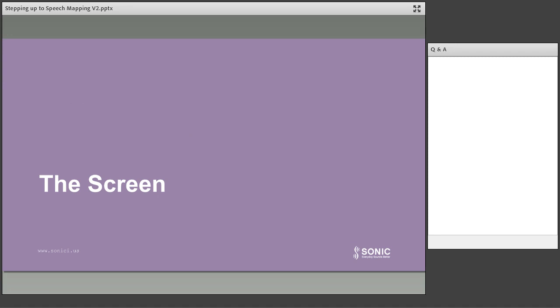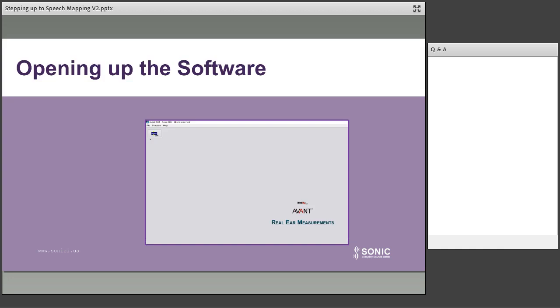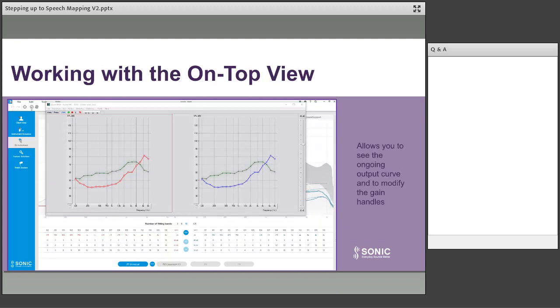Now, the screen is a little bit different than what you'd be used to if you were using real ear insertion gain. But here's a little hint, and this is the way I always love to teach people: when you first open up your Medrx software, you'll see that up in the corner is a little NOA button. If you press that NOA button, it takes you into the overlay mode. In the overlay mode, you can have your fitting software open on the bottom, on the page where you have all of your gain handles, and then you have your REM sitting on top of that. So you don't need to flip-flop from one screen to another. You can see what's happening with your output curves and make modifications on your gain handles down the bottom. Everything is seamless on one screen.